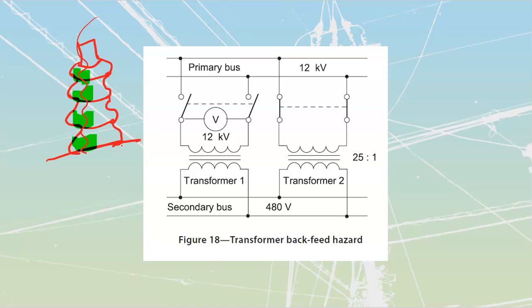They use special cleaners, you can't just throw Windex on stuff. You have to make sure it's not going to be corrosive to the equipment or the cable linings or anything like that. But they clean all this stuff off, and so they have to shut off. They'll still maintain power to the plant. They'll be operating at a reduced capacity because they've only got one of the transformers going. But before they can get in here and clean this, they need to disconnect. So if you've got high voltage setups like this, you're very commonly going to have a second disconnect in the secondary of each transformer.